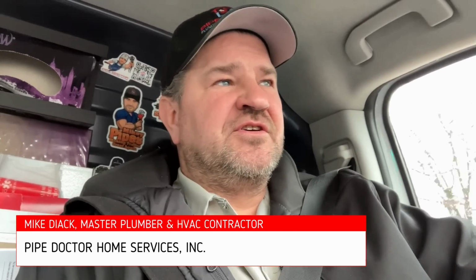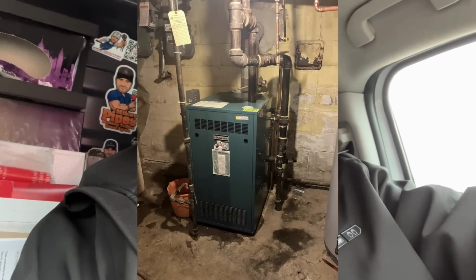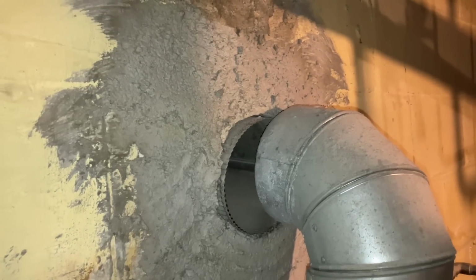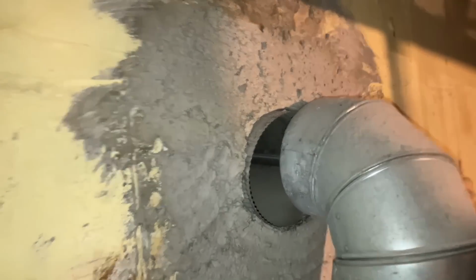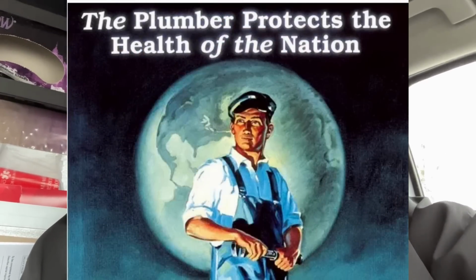Just finished up this 2-hour and 10-minute service call performing maintenance on this Burnham SIN5 140,000 BTU gas-fired steam boiler, atmospheric venting using a chimney. The smoke elbow was not even connected to the chimney breaching and was literally just venting exhaust gases into the basement. Can't make this stuff up. But it reaffirms the motto that the plumbers protect the health of a nation.